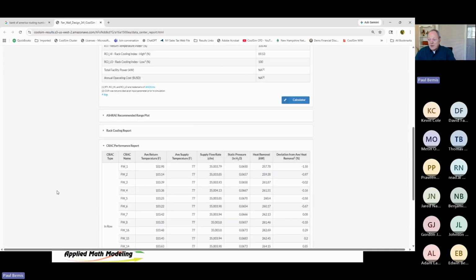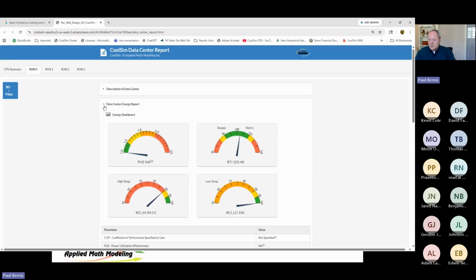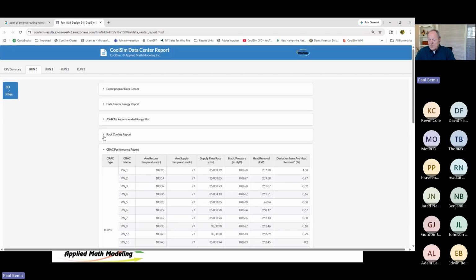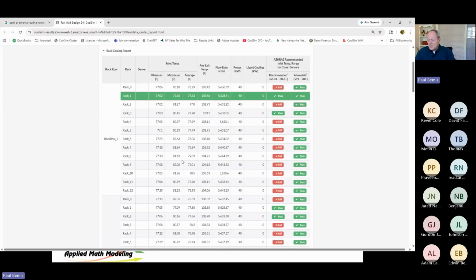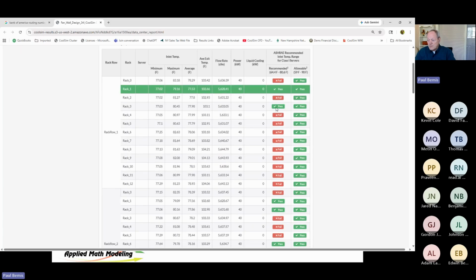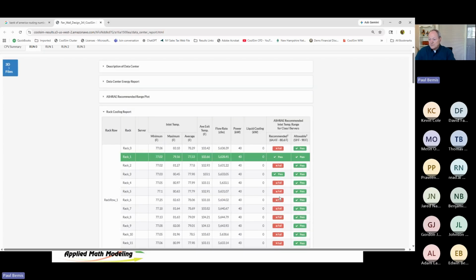And if we look at our racks, so let's close this one. Let's look at our rack report. You see I'm failing. I've got failures here. Some are passing. So this is the recommended range here. You see this design does pass the allowable, which is higher. It goes up to 90 on the inlet temp. But we're having some trouble down here.